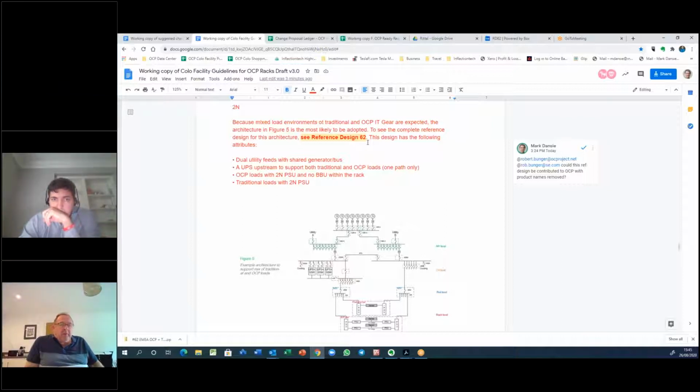Okay. Do you think it's worth adding some sort of caveats to these types of schemes? I mean, they're useful for getting non-electrical end users to be thinking about the paths of delivery of power. But as an electrical engineer, I look at that and, don't take this the wrong way, Rob, I would cringe, because having something like 8 or 9 generators onto one bus without any bus couplers breaking those up would be a huge single point of failure in terms of the generator backup, for instance. So I'm just mindful that if we're putting these in a document, are we endorsing this as the way people should be looking at their facilities?